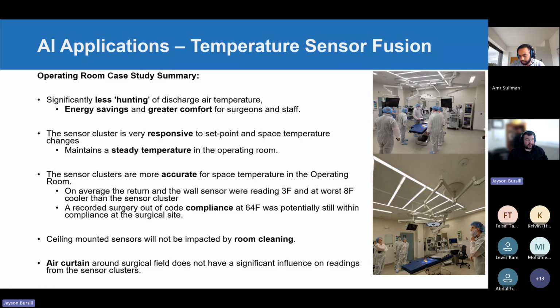It's a tricky space, and cleaning is very important as well, because sometimes in an operating room blood gets everywhere and you have to hose the whole thing down. You could still get blood on the ceiling, but you're less likely to get blood on the ceiling than other parts of the room. So you'll get better response with infrared temperature too, since you don't need the air to blow over it, and you don't have to deal with the thermal mass of a thermostat or other things irradiating a thermostat, like warm equipment.